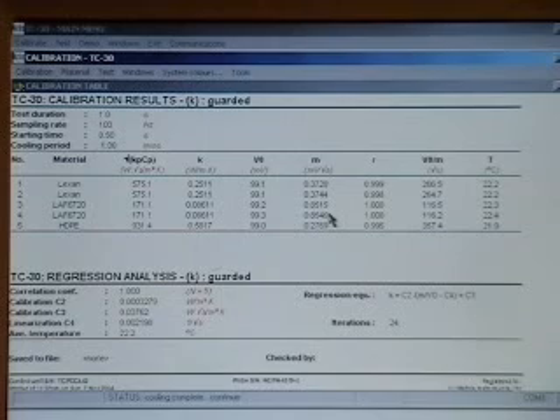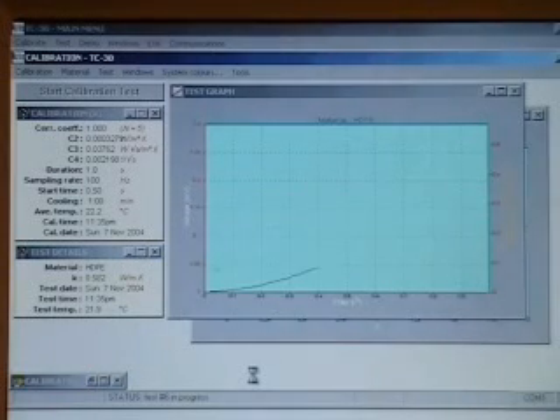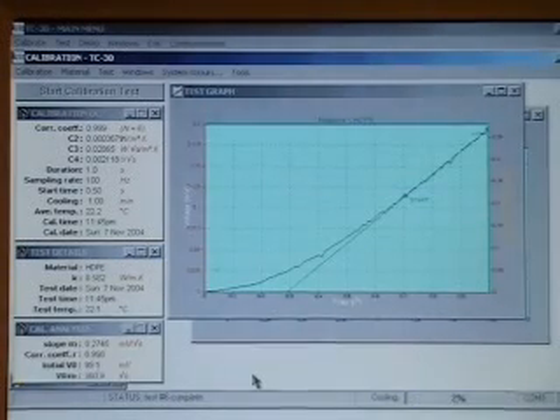This calibration table represents the collected instrument responses against each standard. There eventually will be 6 tests, as each standard is tested in duplicate to ensure reproducibility. We have one last test of HDPE to complete this calibration table. Let's go ahead and test that standard now. After initiating our 1-second test time, there is a real-time display of temperature rise versus time.